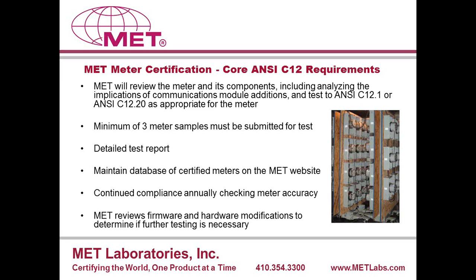It may be single-phase or polyphase type meters, but the metrology is essentially the same in the product, so it's a family. There may be more than 3 meters per test that would need to be tested. And C12.1 has some criteria, some basic guidelines, on how to determine how many samples should run through each test. So all that's looked at up front.